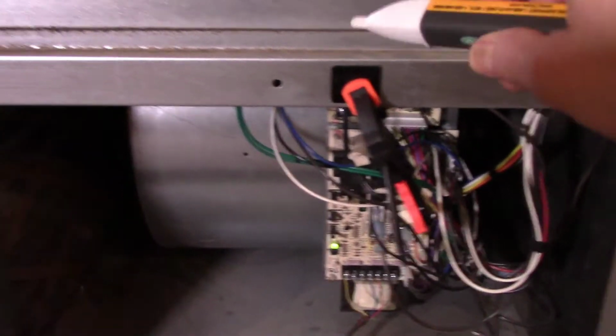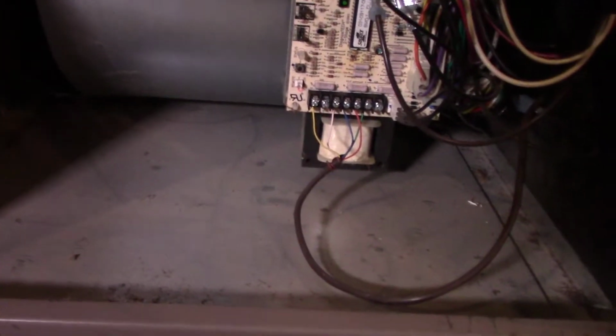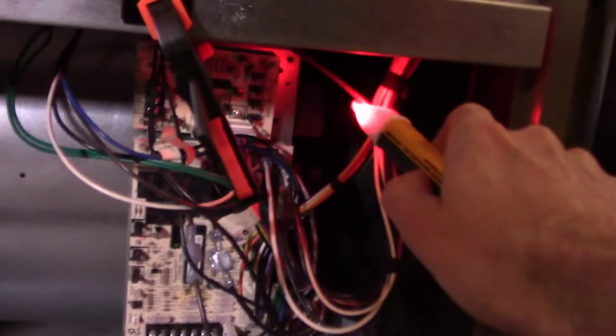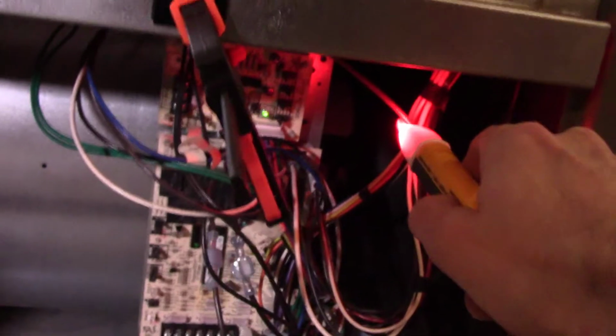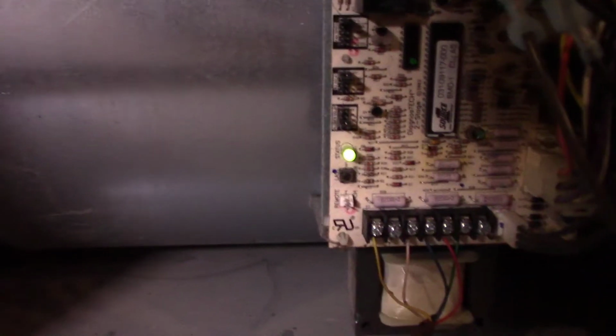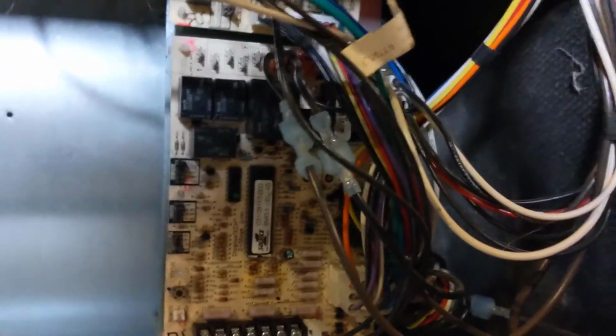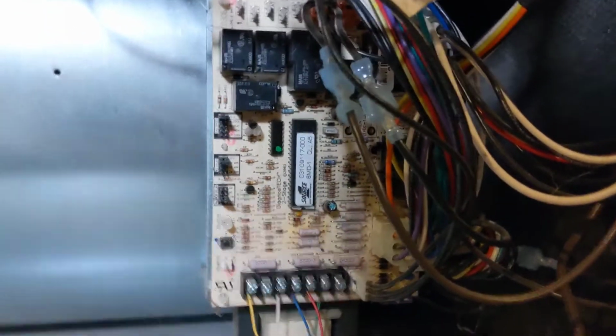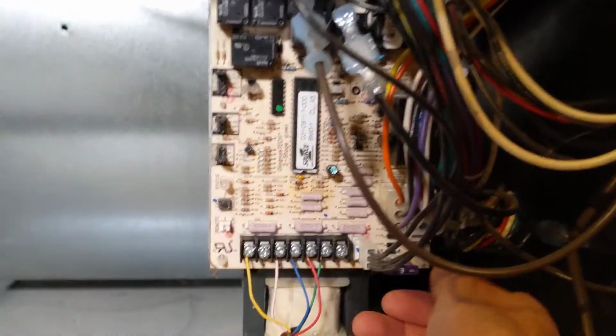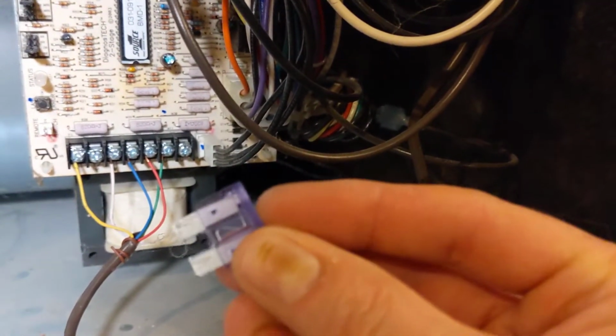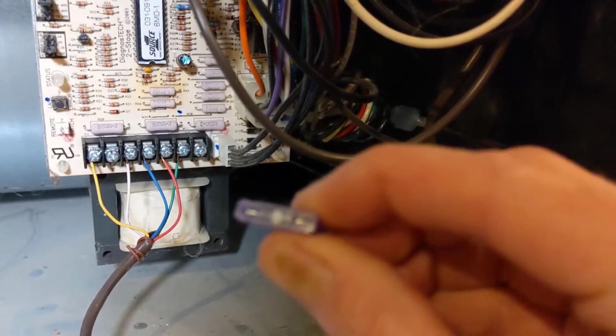So once I clamp the door switch, if you look at this black wire coming off of the switch, that now has voltage, this black wire right here, but you can also see that once I engage that switch, the status light of my board is now showing that it has power. One thing I also mention is the furnace board usually has a 3 or 5 amp fuse on it, so that's always good to check if you're not sure if it has correct power. As you can see on mine, it's kind of hard to see there, it's at the bottom. I'll just go ahead and pull it. They're just like the automotive style, most of the time they're automotive style blade fuses, and this one happens to be a 3 amp fuse.